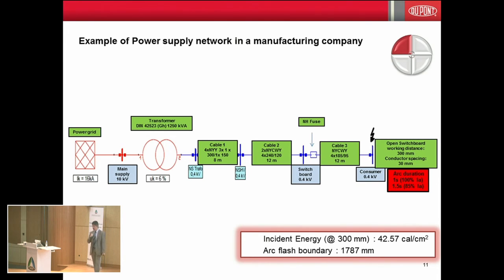To give you an idea, in our laboratory in Switzerland we have one of the 3 labs available around the world to do arc flash testing. There's only 3 labs, with a 4th under development in Brazil but not yet accredited. When we generate an arc, we generate a hot plasma with temperatures between 15 and 20,000 degrees, more or less 4 to 5 times the temperature of the sun.